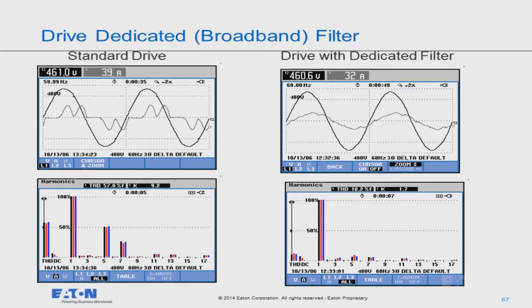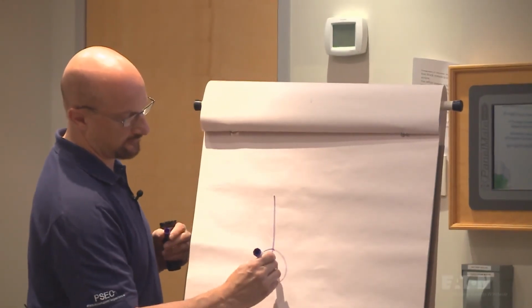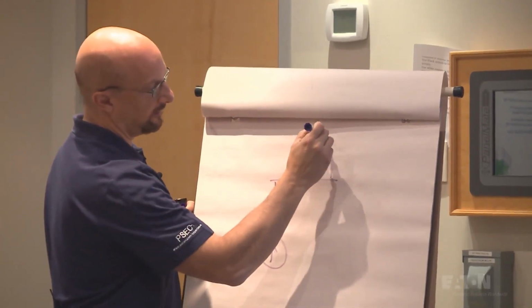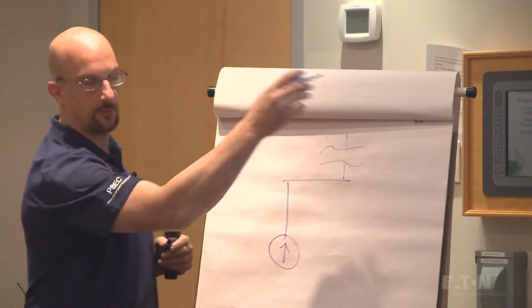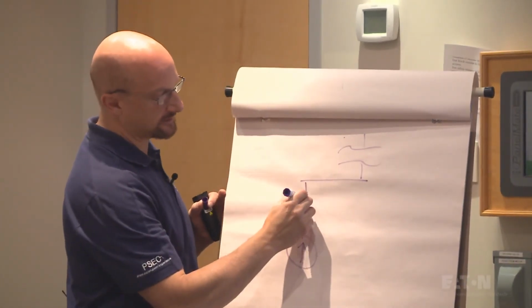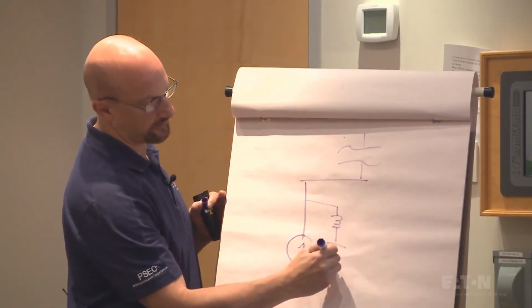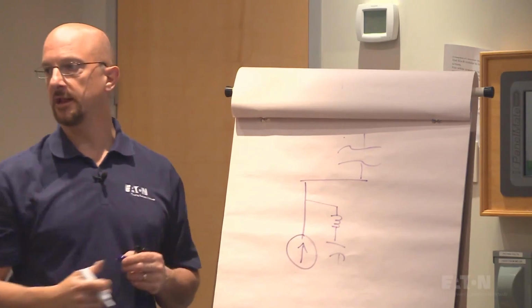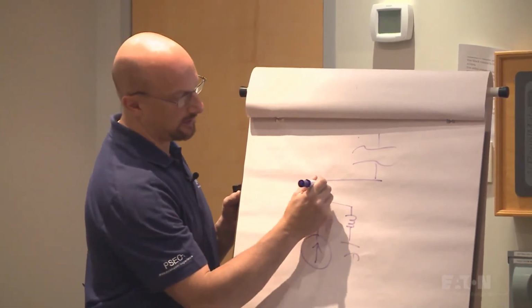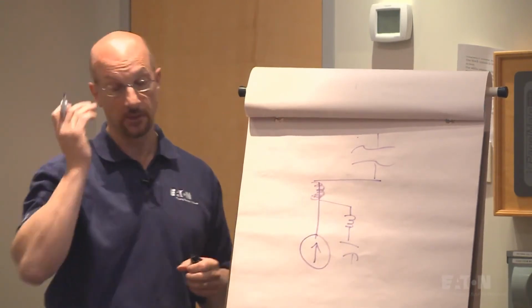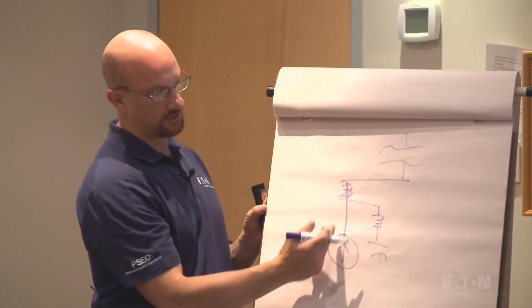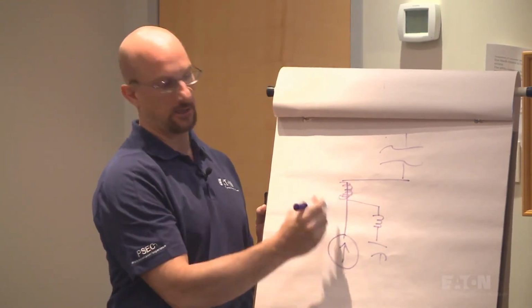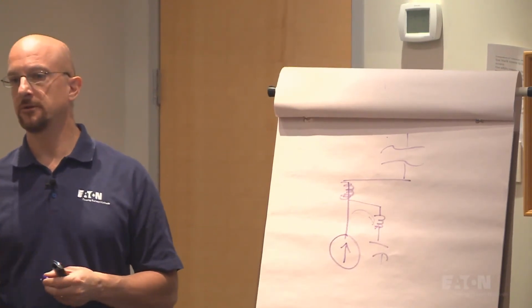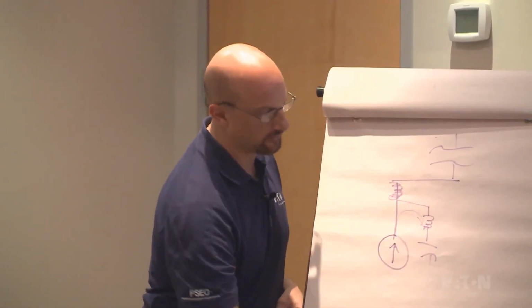This is a broadband filter. Here's my harmonic source, my drive. Normally, I put this drive in, and it pumps current back up through the system. What I do is I hang this filter off of here, which is a reactor and a capacitor. Okay, and the harmonic current wants to go into that. That's a standard filter, but a broadband filter also adds a big inductor here, like a 10% reactor. Okay, what that does is it forces the current to get to this point and it says, wait a minute, I don't want to go back that way. I want to go this way. So by doing that, you end up with this being a much more effective filter.